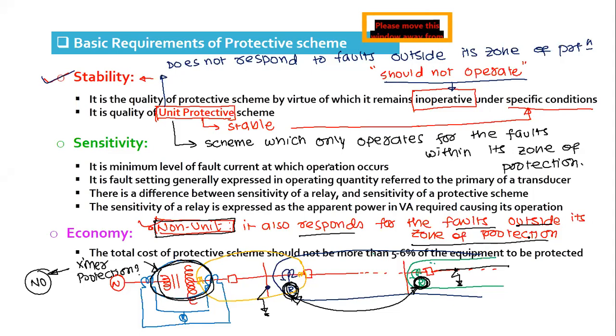So a power system consists of different schemes. Some of them are unit, some of them are non-unit, depending upon the application required. So the stability criterion is a criterion for unit protection. When you have a unit protection scheme, it is compulsory that it should not respond to the faults outside its zone of protection.